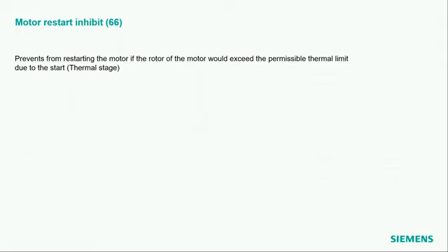What this function cannot do is to look into the future. If the start is longer than the normal start, of course, we will exceed the maximum temperature. This is then an extraordinary situation. Okay, it prevents multiple starts and stops in a short time interval. So we have basically a thermal stage. This is the first sentence here. So I calculate what is the maximum temperature from which I can still make one standard startup.